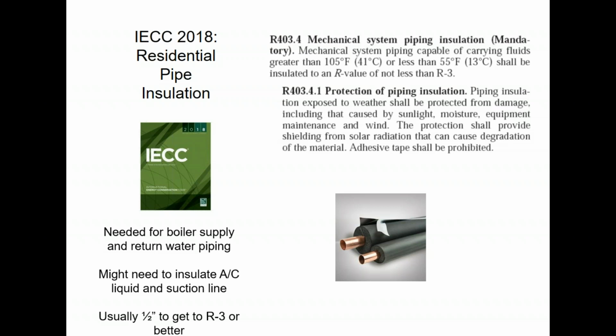Refrigerant systems, you're going to have to insulate those as well for your liquid and suction lines. They're very likely going to be above 105 and below 55. When you're doing this insulation, the code requires you have an R3 insulation. A lot of the manufacturers of the insulation for refrigerant line sets are not good about telling you the R value, so you've got to go dig around in their tables to figure it out. As a general visual way to think about it, usually for Armaflex type stuff, 1/2 inch insulation is what you're going to need to get to an R3. So that may be more insulation than you're used to putting on there.